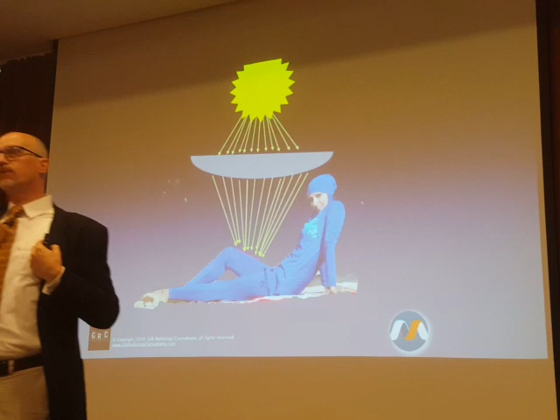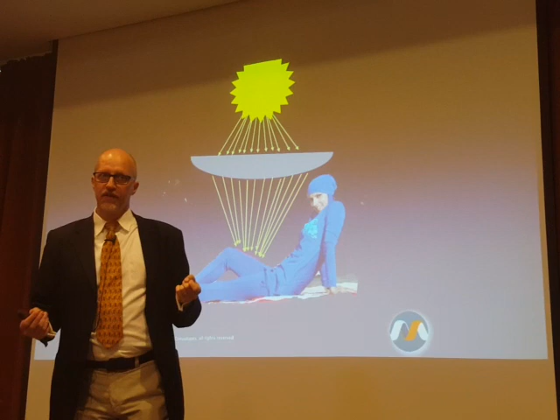Within our patients, we have a number of lenses, potentially, in the form of implants and devices that may allow for the focal concentration. It doesn't change the amount of RF power that we're transmitting. All it does is it changes where in the patient's body it collects or deposits. So RF burns are not necessarily an indication that your machine is malfunctioning. The machine is transmitting, in theory, the same amount of power. It's that something about the position of the patient or things that are in the bore with the patient, or the large caliber body loops that the patient forms with their own tissues, that it's these elements that act as lenses, act as opportunities to focus the energy from the radio frequency power and concentrate it.